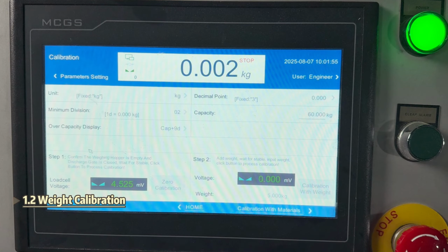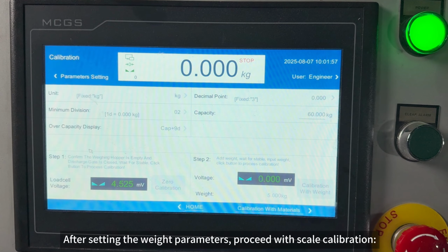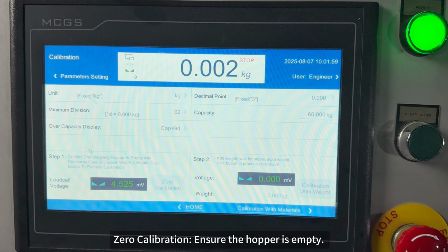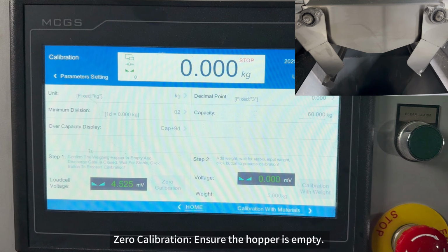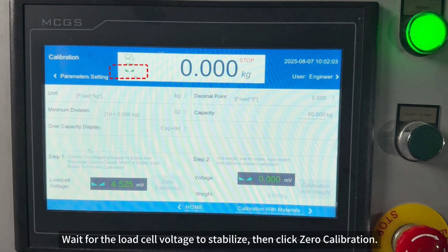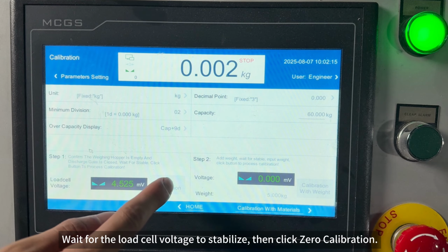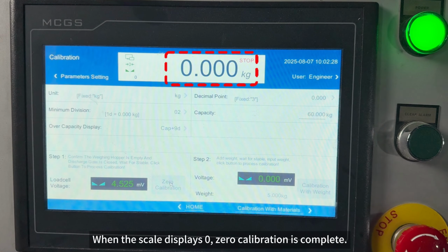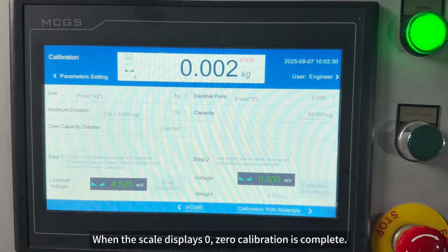1.2 Weight calibration. After setting the weight parameters, proceed with scale calibration. 0 calibration. Ensure the hopper is empty. Wait for the load cell voltage to stabilize, then click 0 calibration. When the scale displays 0, 0 calibration is complete.